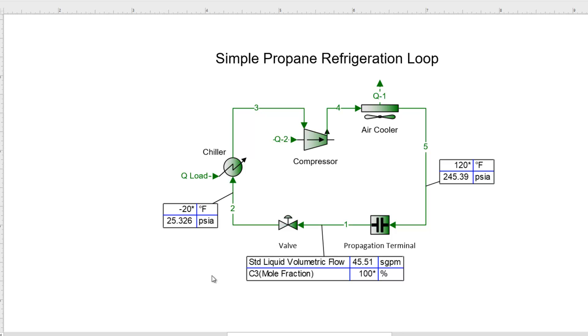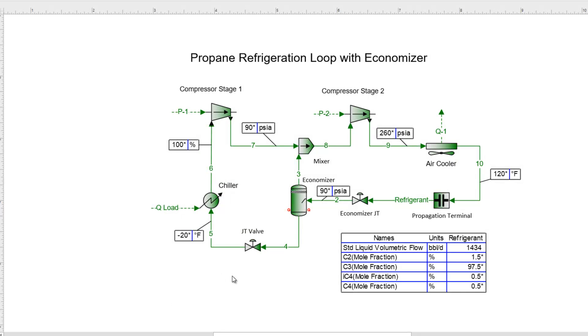That's the basics of these closed loops as we see in refrigeration loops. I do want to show a second flow sheet — a more complex example — just to illustrate that you can have more complex closed loops. In this case, we've added an economizer and broken our compression into two stages. It's specified essentially the same way; we just also need to define our economizer pressure and our first compression pressure, using that same propagation terminal to handle the closed loop.